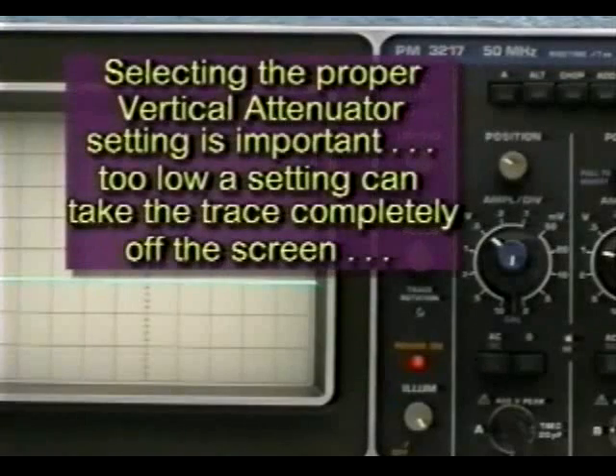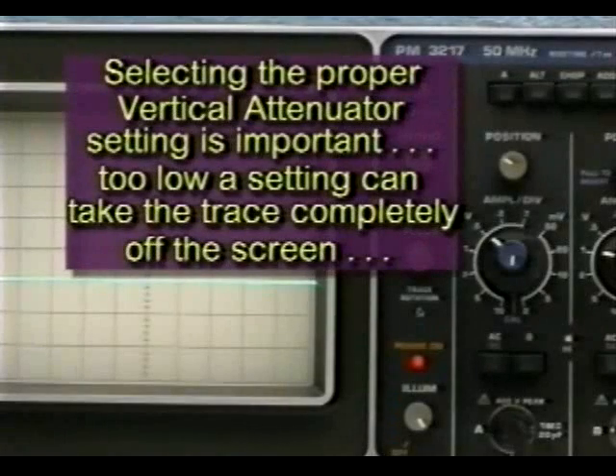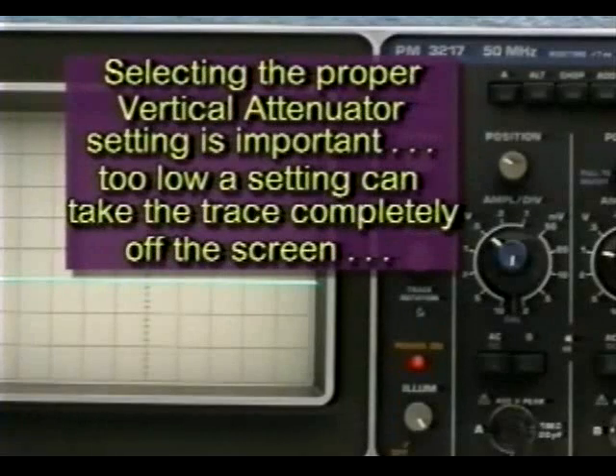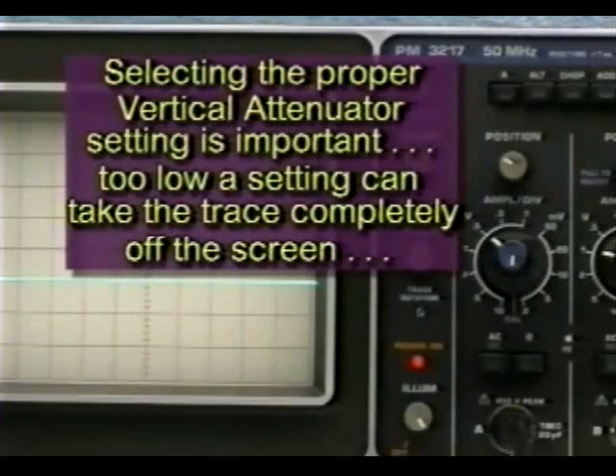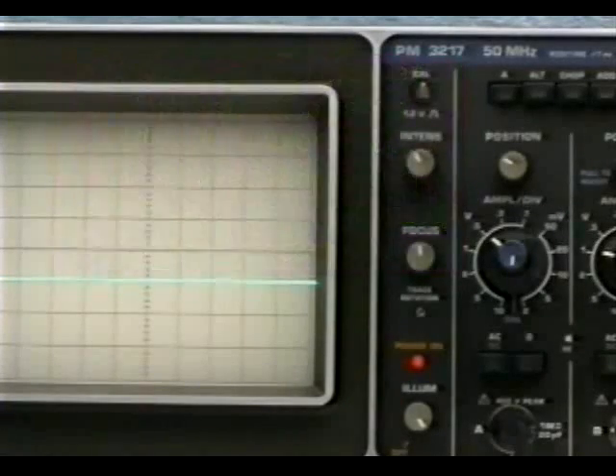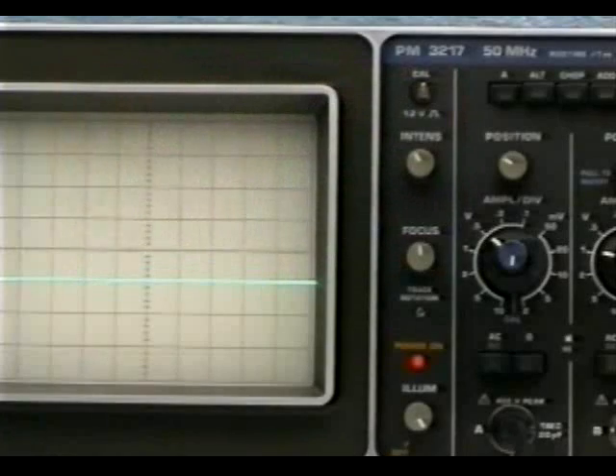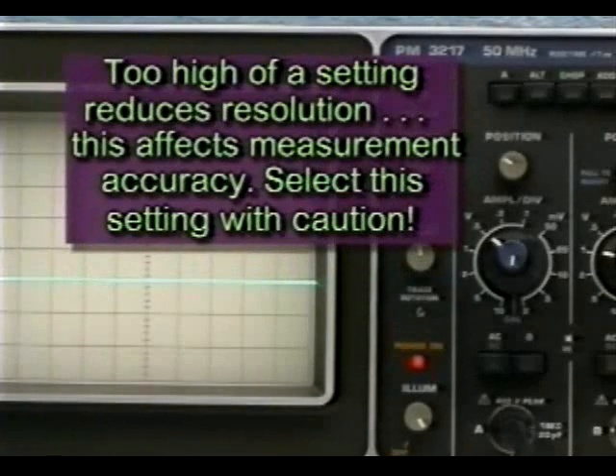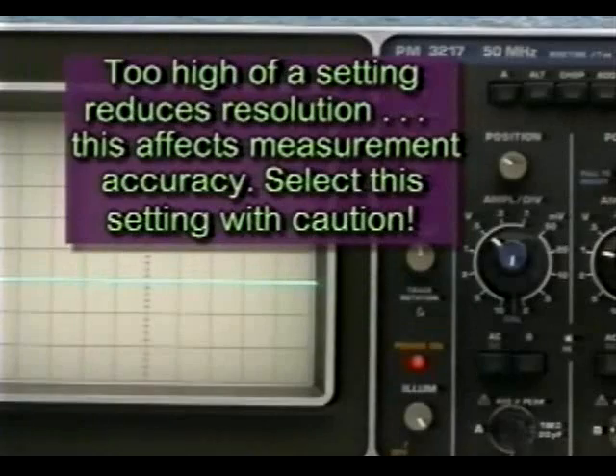Setting the vertical attenuator control to the lowest setting possible without allowing the beam to deflect off the screen will provide you with the best measurement accuracy. Selecting too high of a vertical attenuator setting compromises resolution. Try to avoid this whenever possible.